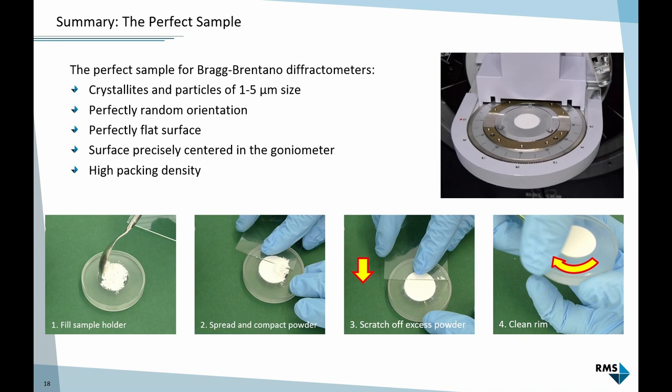To summarize, what should we do for the perfect sample during preparation? We have to make sure crystallites and particles are in the range of 1 to 5 micrometers. They are randomly oriented, that the sample surface is perfectly flat. Once on the instrument, it's perfectly centered on the axis of the goniometer. We also want high packing density - don't just sprinkle powder, but compact it into the sample holder because this reduces penetration depth and helps getting high resolution signal.